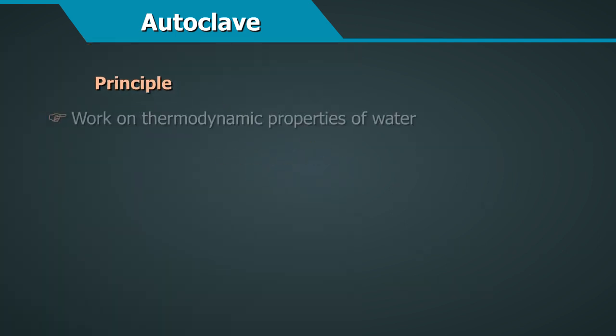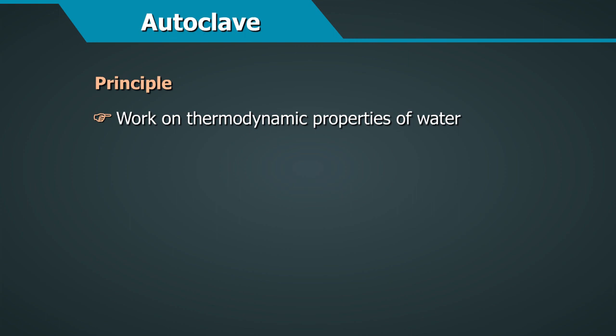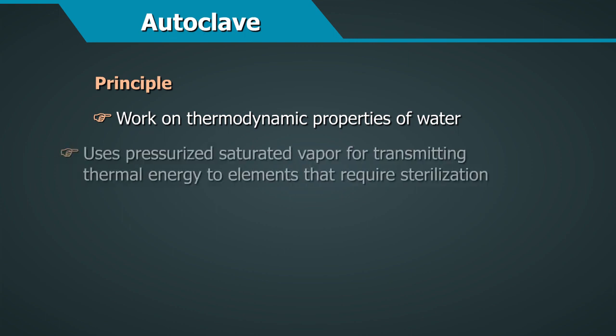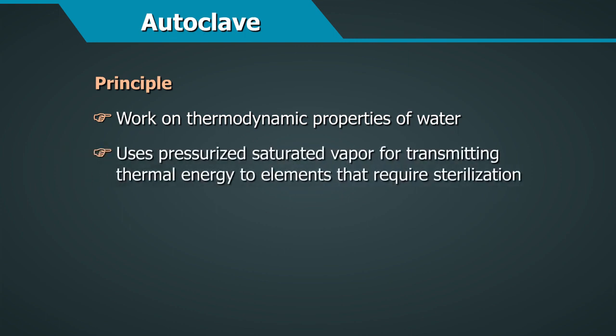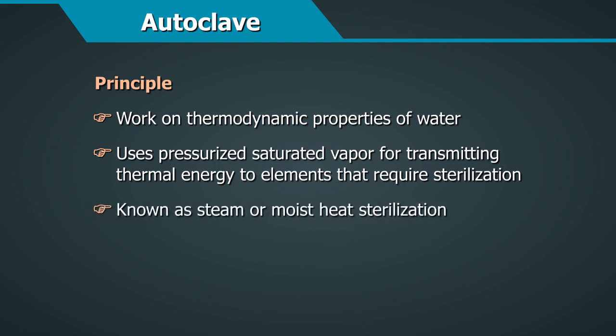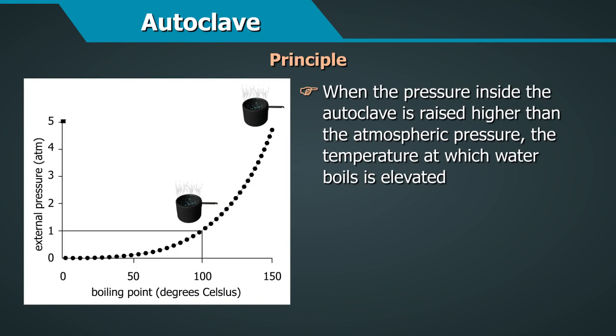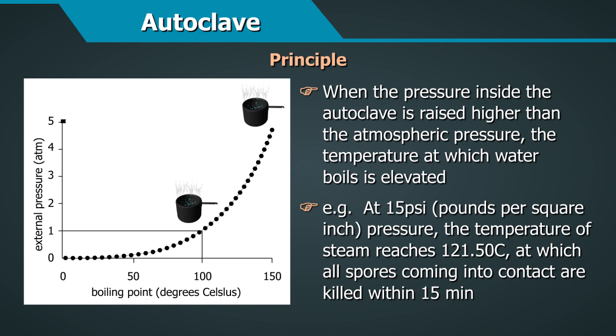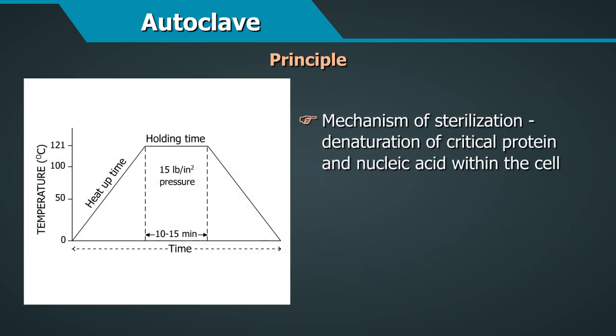Autoclaves work by taking advantage of the thermodynamic properties of water. They use pressurized saturated vapor for transmitting thermal energy to elements that require sterilization. This method is known as steam or moist heat sterilization. When the pressure inside the autoclave is raised higher than atmospheric pressure, the temperature at which water boils is elevated. For example, at 15 psi pressure, the temperature of steam reaches 121.5 degrees centigrade, at which all spores are killed within 15 minutes.